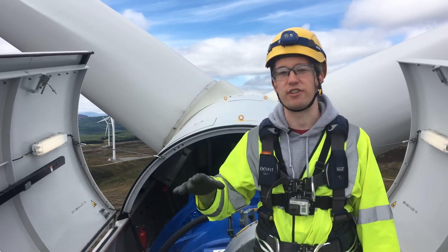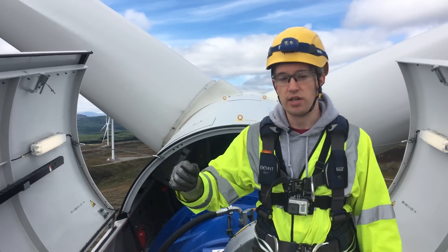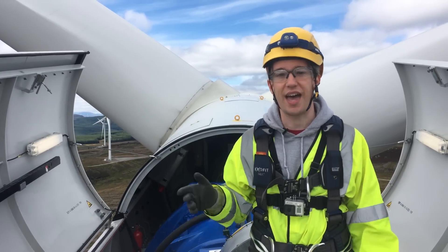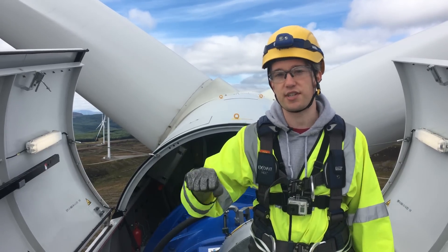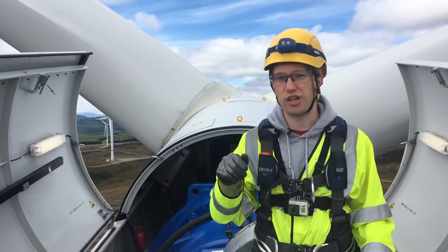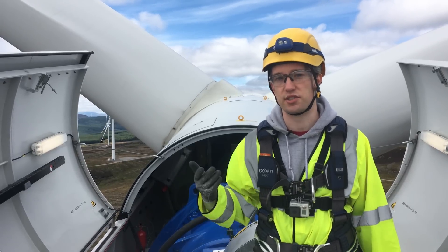Homes and factories will literally suck the kinetic energy out of that turbine to cover the gap, starting to slow it down. But that won't cause a problem for about 60 seconds or so, and in that time the National Grid Control Centre will throw another nuclear rod on the barbie and up the power output from other stations, and it'll cover the demand. But that relies on having enough rotational mass — enough system inertia, as it's called.